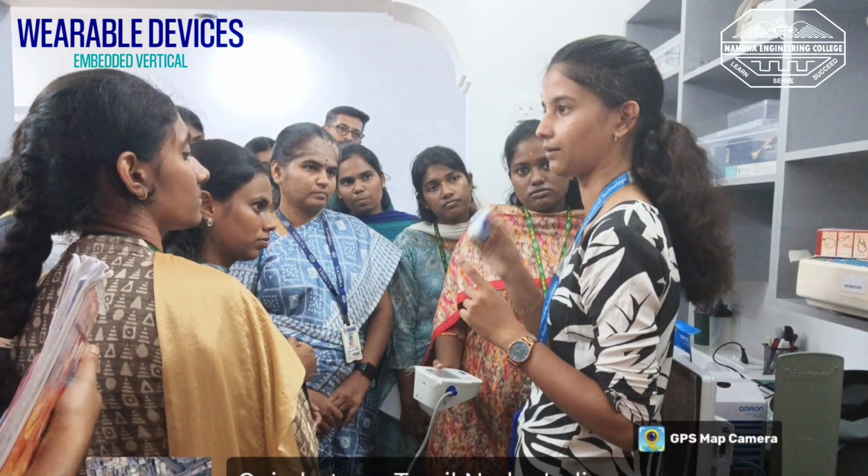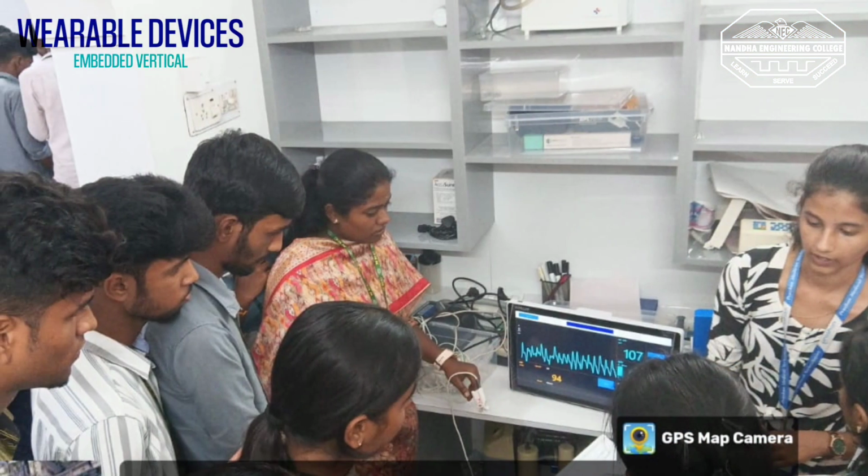Ventilators operate in various modes like volume controlled, pressure controlled, and assist controlled, depending on the patient condition. Communication interfaces such as UART, CAN, and Ethernet allow integration with hospital systems and remote monitoring. Power reliability is ensured through medical grade supplies and battery backups. As electronics and communication engineers, our role is crucial in designing, testing, and maintaining these systems with precision and safety. Understanding ventilators not only depends on our grasp of embedded systems and sensor integration, but also connects technical expertise to real world impact, saving lives through engineering.